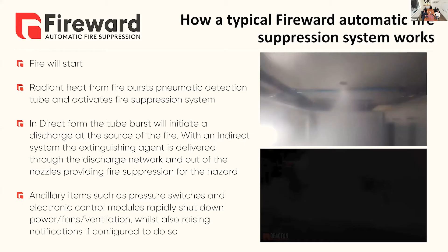So as you can see, that fire that you just saw was what we call a worst case scenario fire, very similar to the first one you saw in the video, where you've got all the combinations of wood soaked in diesel, a spraying flammable fluid, a high airflow environment, and that's what dictates the high performance systems that we fit at Fireward. We exceed everyone that has a certain approval for heavy equipment, and it's because our system is designed and tested to extinguish every conceivable fire inside an engine bay. And we have systems that can be fitted to anything from a 3.5 ton forklift to the largest construction equipment you'd see on site.